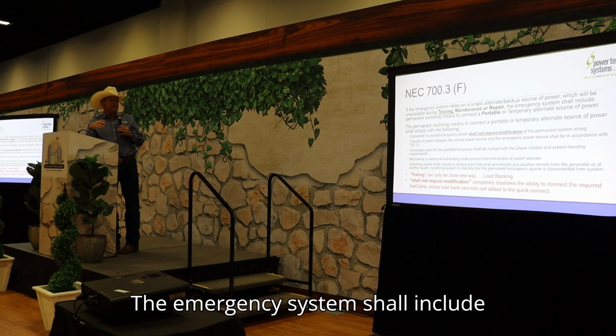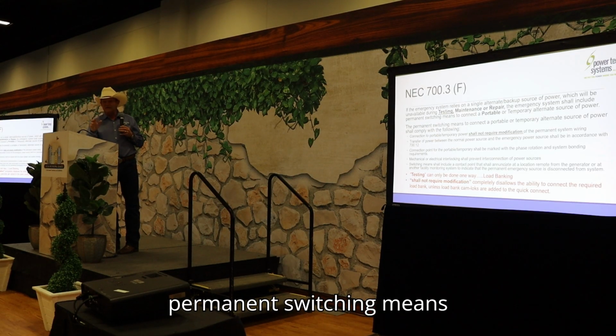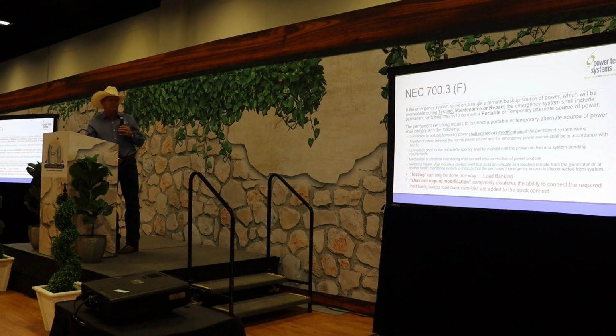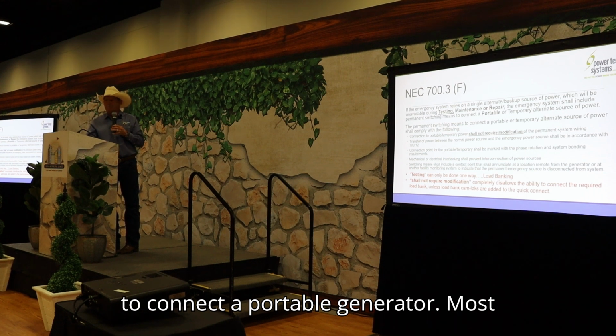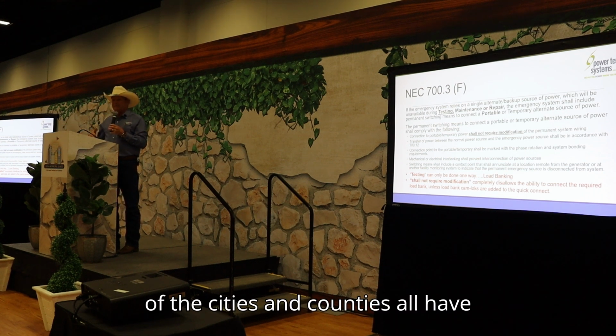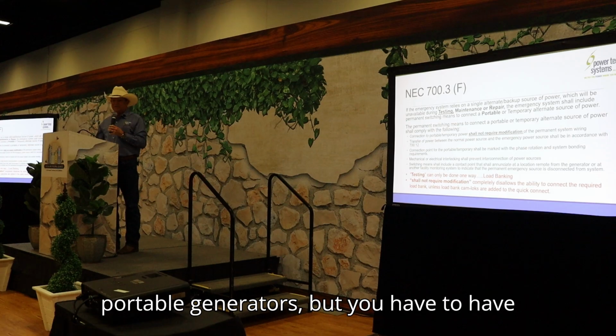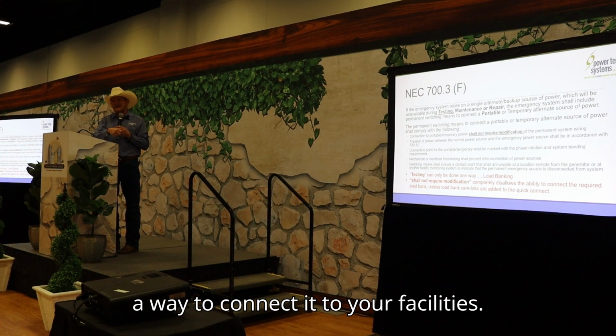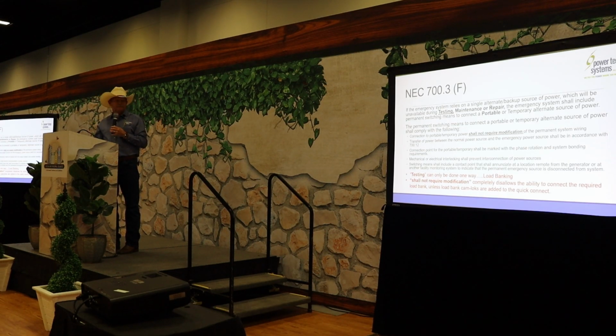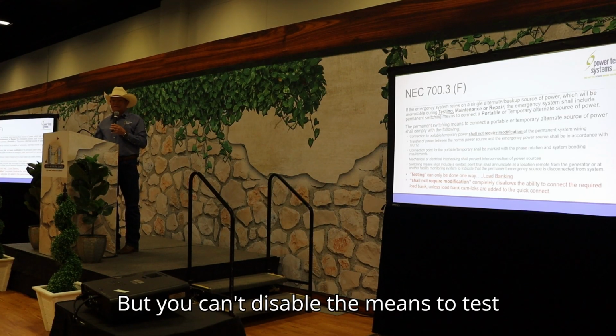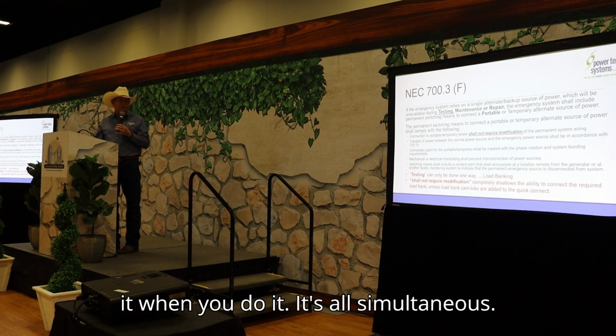The emergency system shall include permanent switching means to connect a portable generator. Most cities and counties have portable generators, but you have to have a way to connect it to your facilities. But you can't disable the means to test it when you do it.